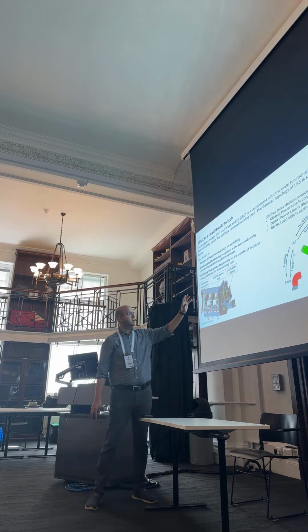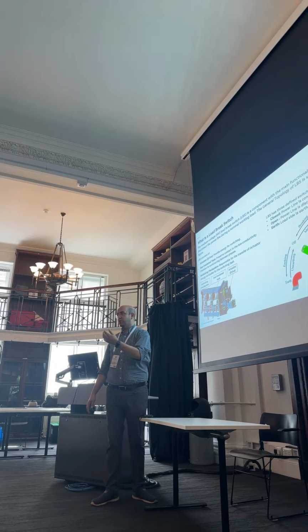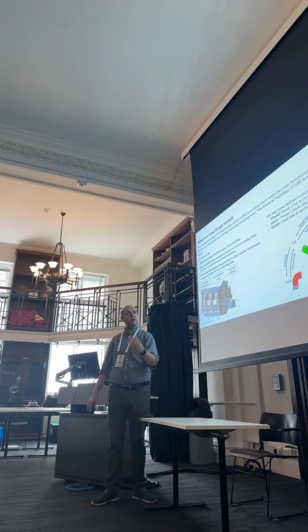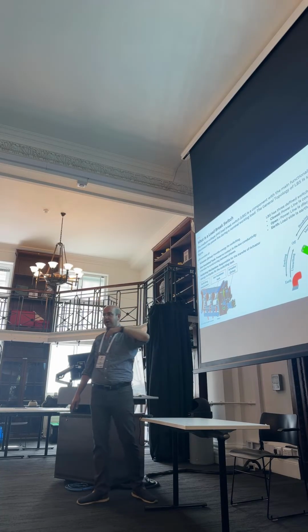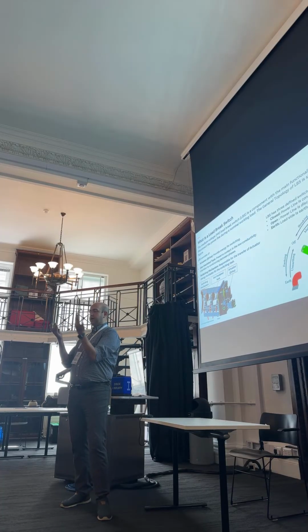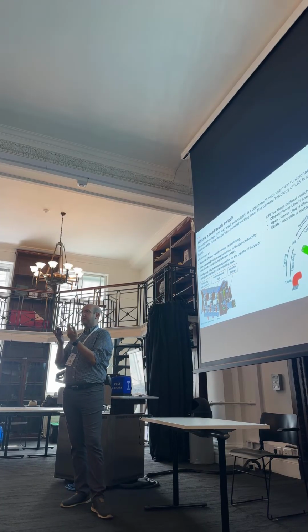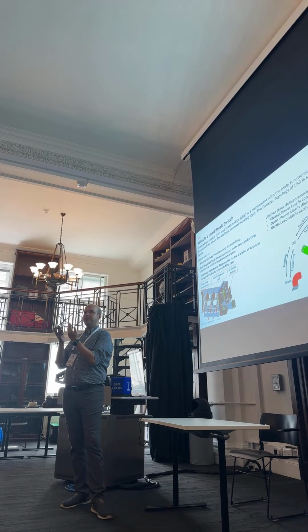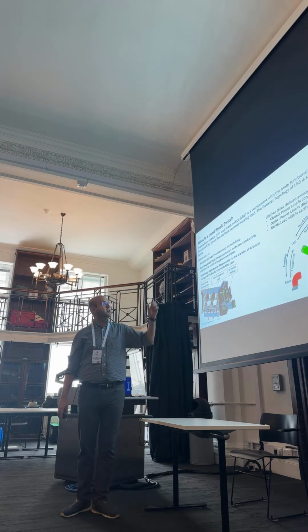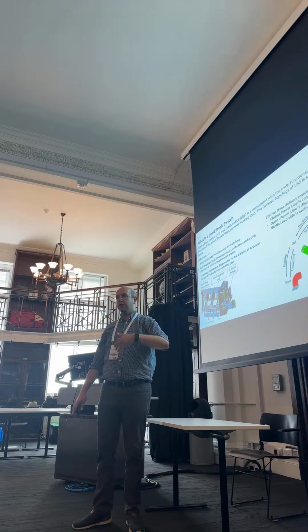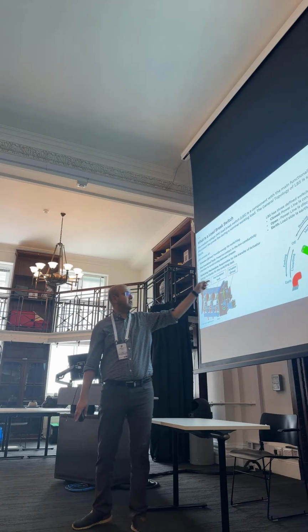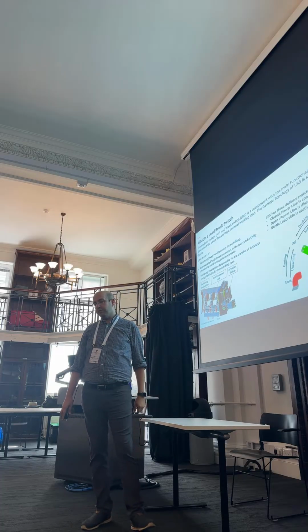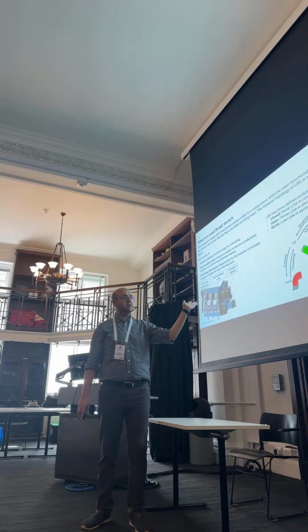These devices need to disconnect and connect the line really fast, so the mechanical operation must be very quick. To give an idea, at the tip we need to achieve 10 meters per second speed to properly break and connect the arc. If the speed goes above or below that, the arc burns for a while and the whole substation can explode, so it's critical to keep precise timing for breaking and closing the arc. A normal load break switch has four operations: making the line so electricity can pass, disconnecting or breaking the line, and operator or technician modes called earthing and unearthing.